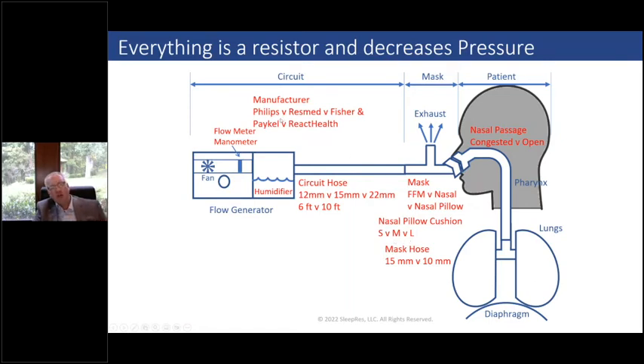Then you go to the manufacturer. Philips masks have more resistance than ResMed, Fisher-Paykel, and React Health masks. They're all pretty similar, but Philips has more resistance, particularly in their larger cushion, because they try to make all their cushions the same. So if you use a Philips mask with a ResMed blower, you're going to drop the pressure. If you use a ResMed mask with a Philips blower, you're going to get higher pressure, because those manufacturers want you to use their mask and designed it for that particular resistance.